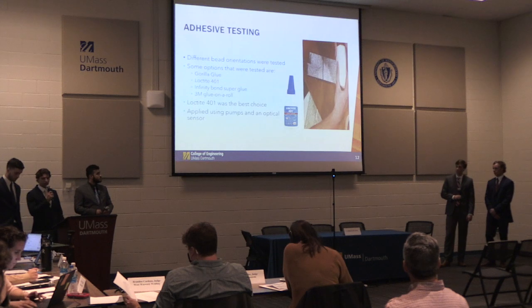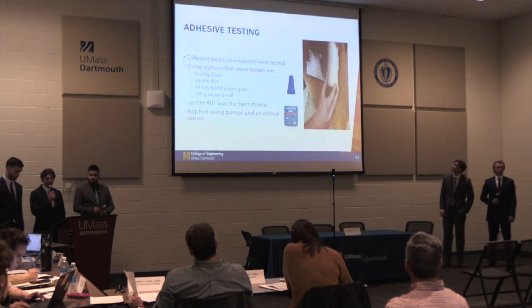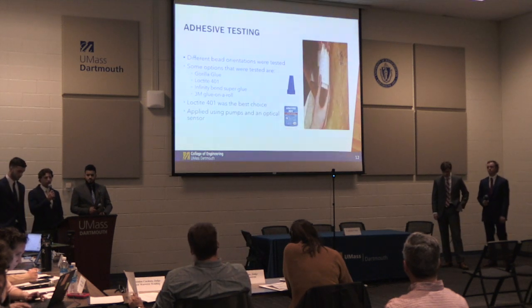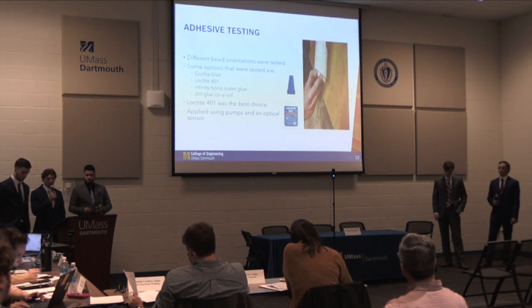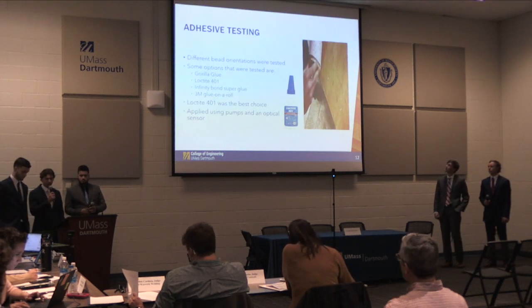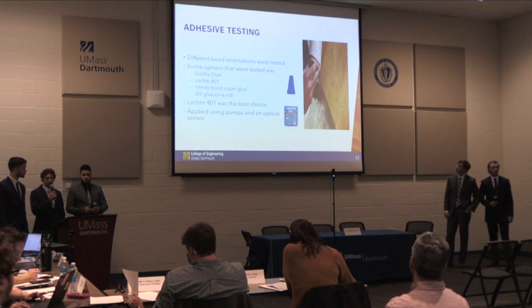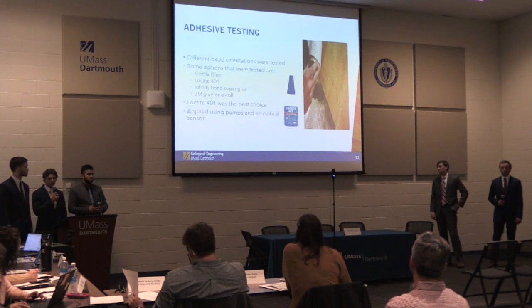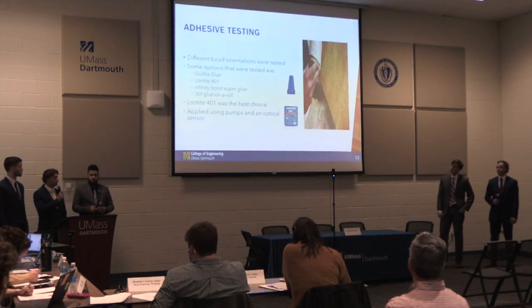For the design we went with, we had to test multiple adhesives. We tested a bead pattern going across the width of the fabric, applying dots to the tabs, as well as applying a bead going the full length of the fabric. We decided on Loctite 401. We thought that was the best adhesive based on all the ones we tested — it didn't react with the fabric, it bonded quickly, and it stuck to both the fabric and the substrate.